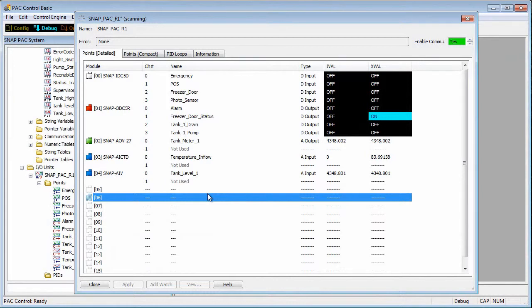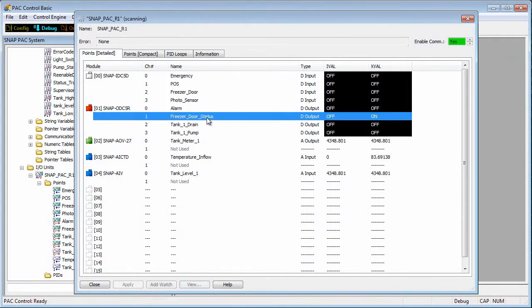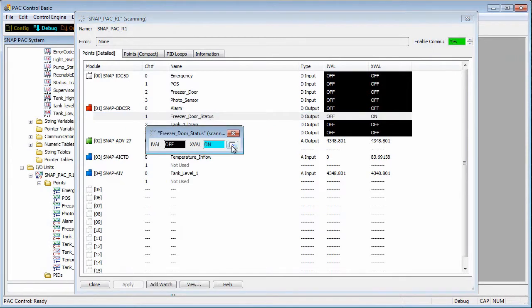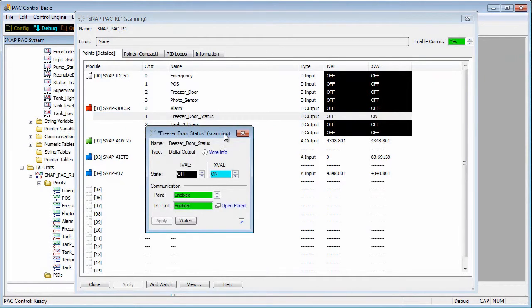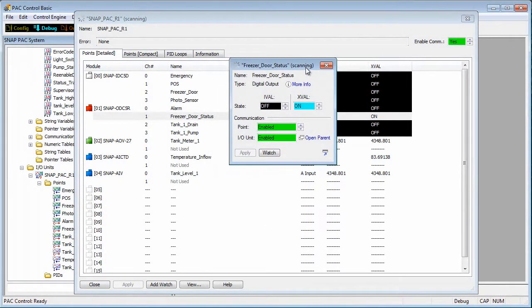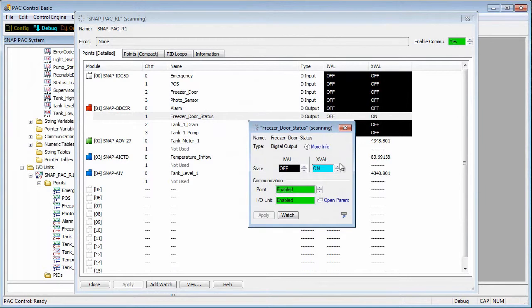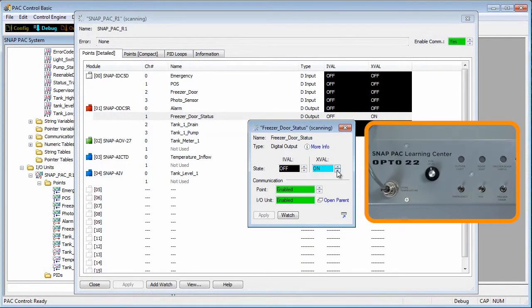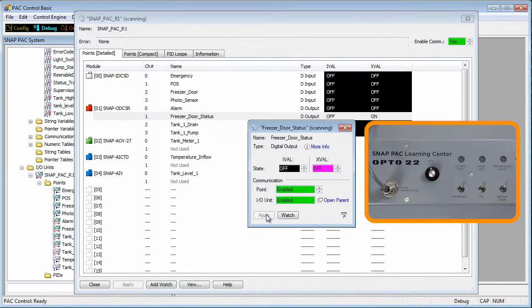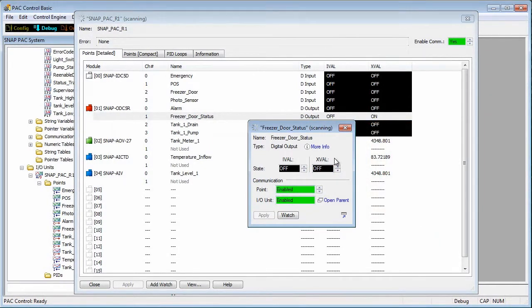Speaking of which, let me show you how to do that. First, I'll double click on a digital output point and expand the window. Because I want to force an output on the I/O unit, I'll change the XVAL to on and click apply. Now the LED is on. I'll switch it to off and click apply and I've turned off the point.